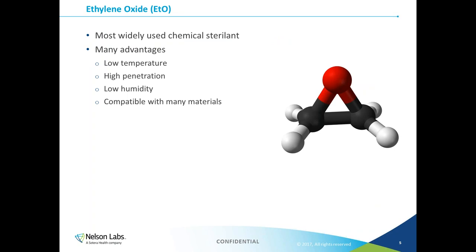Let's jump into the discussion on ethylene oxide. Ethylene oxide is the most common sterilization method in the medical industry — over half of all medical devices use this method. It is a colorless and extremely flammable gas, primarily used as a precursor in manufacturing for products such as ethylene glycol, which you might know as antifreeze, and various other plastics or polymers. Less than 1% of all EO manufactured is used for sterilization. The EO sterilization cycle involves placing items into a chamber where humidity and EO gas are introduced. The humidity is a very important part of the process — without it, the sterilization kill mechanism could not occur. After a predetermined amount of time, the gas is flushed from the chamber and items are allowed to off-gas to ensure most EO residual has been removed.